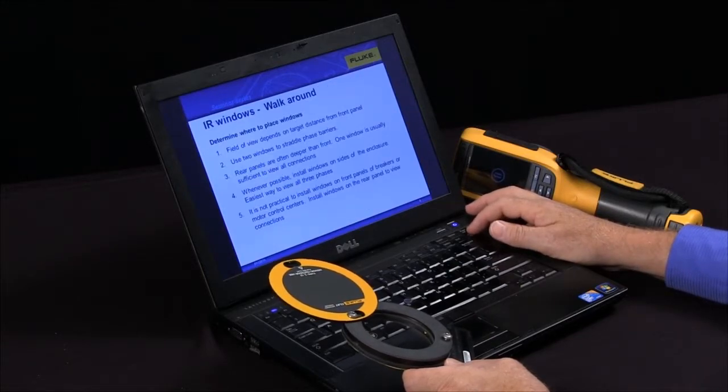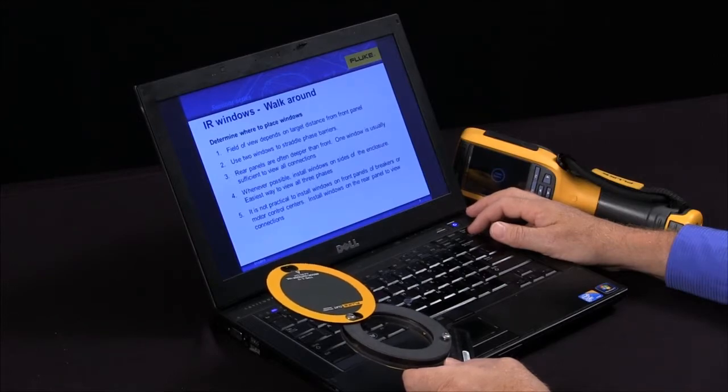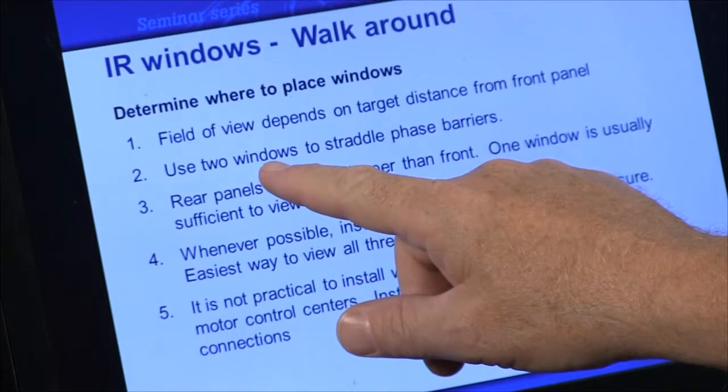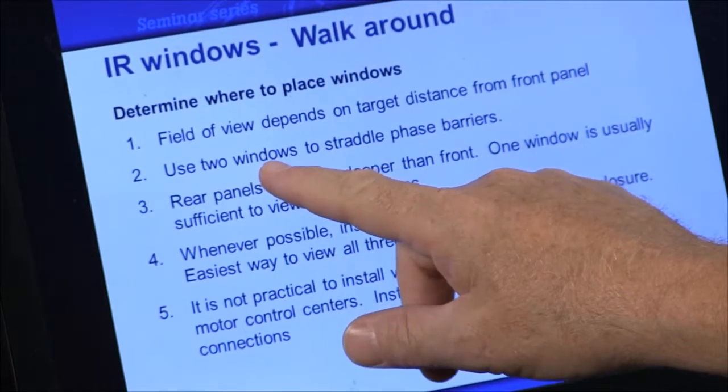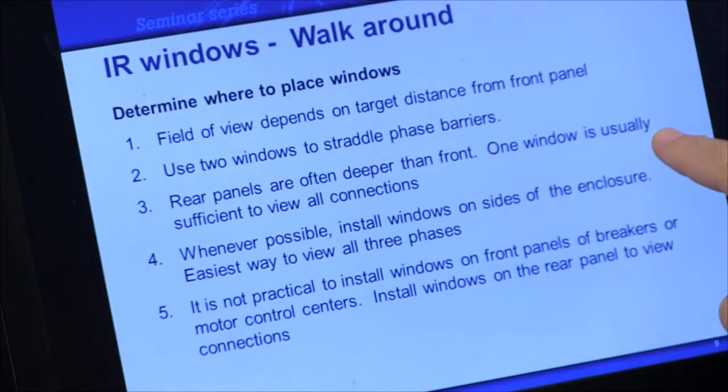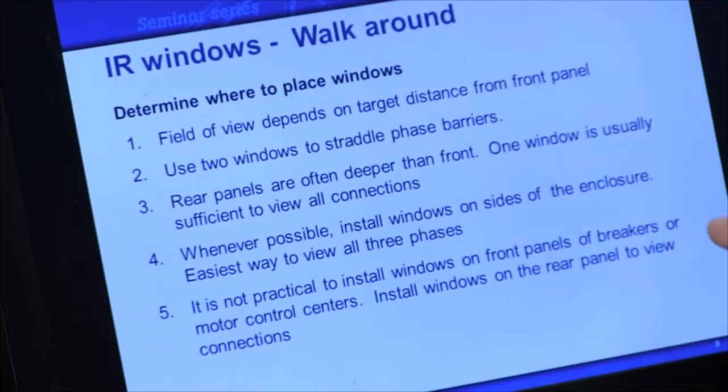So to determine how many windows you need, it really helps to walk around and look at your cabinets. If you have things like phase barriers, there's ways we can straddle that with two windows so you don't need to have three. If you're working with rear panels, they're often deeper than the front, and sometimes it's not practical to install the window on the front panel. If you install it on the rear or the side, you can see very well.